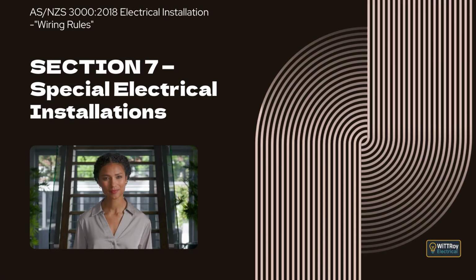Clause 7.2.4.6 Fire-separated portions of a building. This clause explains that where switches controlling safety services are installed in a fire-separated portion of a building and provided on the switchboard within that fire-separated portion, they are regarded as main switches and must be arranged in accordance with Clause 7.2.4. It explains that parts of a structure separated by a fire resistance level of at least 120/120/120 minutes may be treated as a separate building for this purpose.